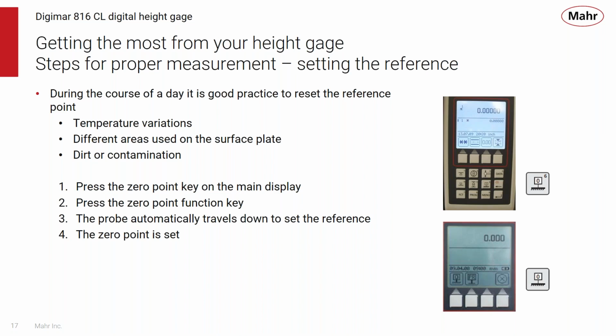And during the day, you want to wipe off the surface plate to take off any dust or contamination that might have fallen on it. You can wipe off the surface plate, reset your 0, and that'll improve the performance of the measuring system. So you press the zero function or 0 point key, and then you press the function for doing your zero. The probe is going to come down automatically and set the reference, and now your 0 point is set. You should do that a number of times during the day to improve the performance of the measuring system.